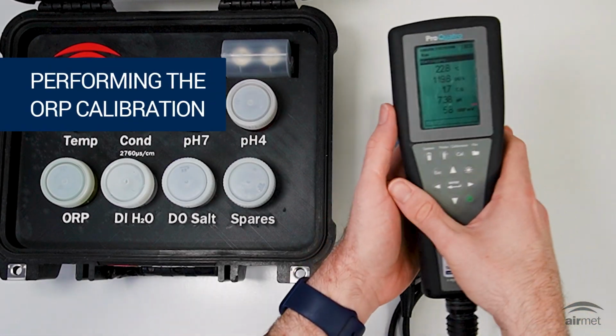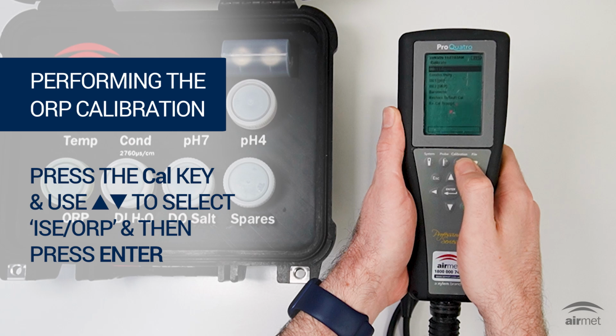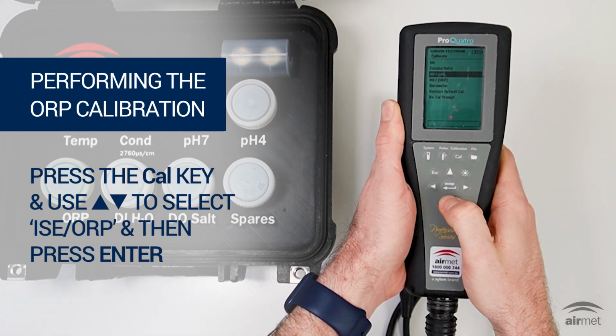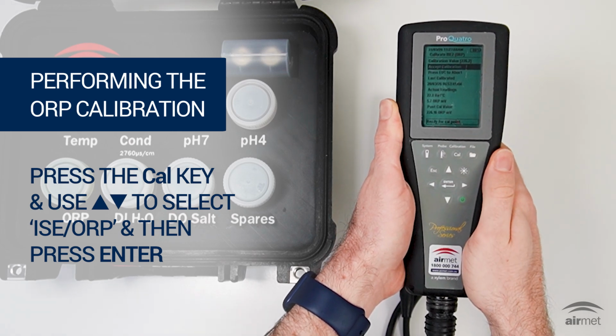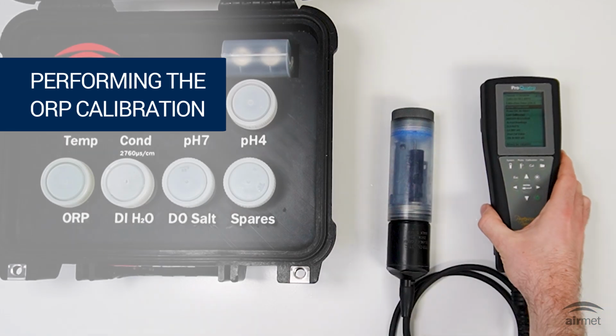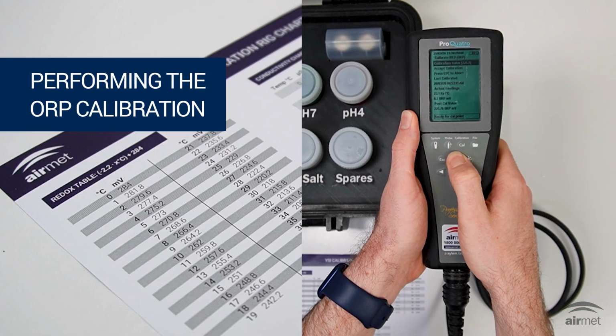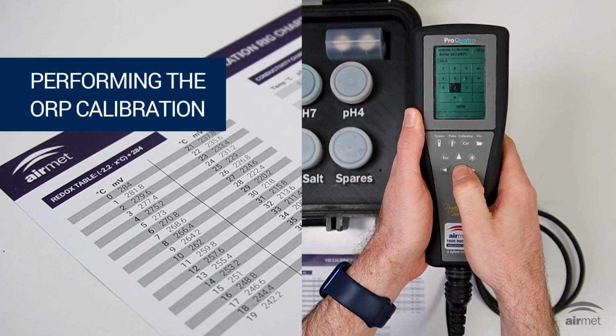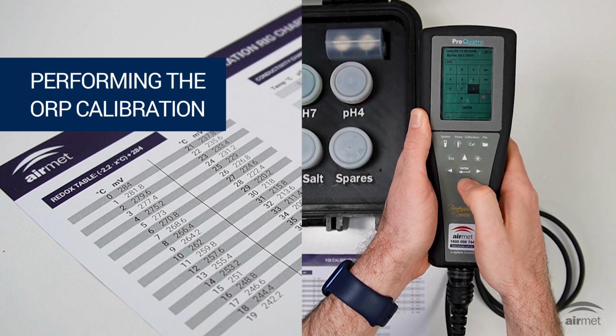Performing the ORP calibration. Press Cal, highlight the ISE/ORP and press Enter. This will select the ORP from the calibration options. Enter the correct millivolt value for that temperature and confirm that the instrument recognizes the standard.